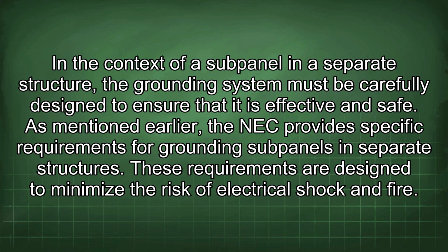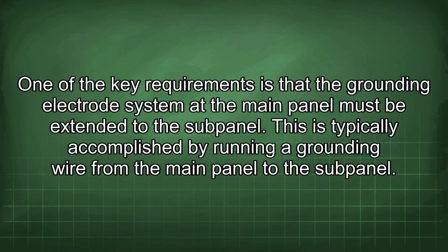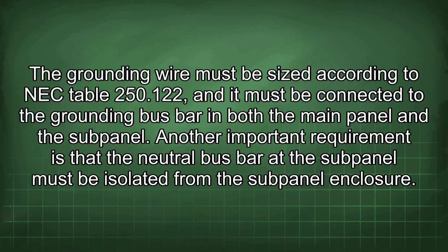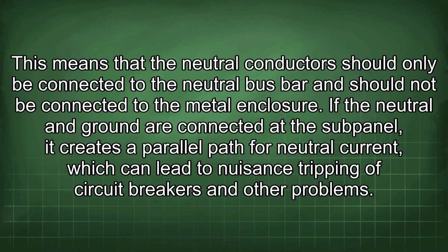As mentioned earlier, the NEC provides specific requirements for grounding subpanels in separate structures. These requirements are designed to minimize the risk of electrical shock and fire. One of the key requirements is that the grounding electrode system at the main panel must be extended to the subpanel. This is typically accomplished by running a grounding wire from the main panel to the subpanel. The grounding wire must be sized according to NEC Table 250.122, and it must be connected to the grounding bus bar in both the main panel and the subpanel. Another important requirement is that the neutral bus bar at the subpanel must be isolated from the subpanel enclosure. This means that the neutral conductors should only be connected to the neutral bus bar and should not be connected to the metal enclosure.